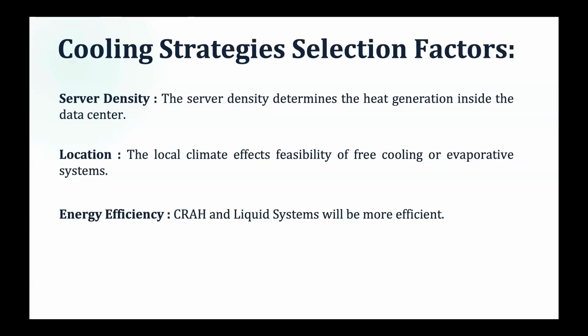Okay. So how can you achieve cooling energy efficiently and without compromising on performance? The first strategy we can use is airflow management. The cold conditioned air coming from an AC unit should gain temperature inside the data center only by passing through the servers and absorbing the heat in those servers. If the cold air escapes through gaps where it is not supposed to and mixes with the return air, then the energy used for cooling is wasted. So one of the strategies in airflow management is hot or cold air containment.